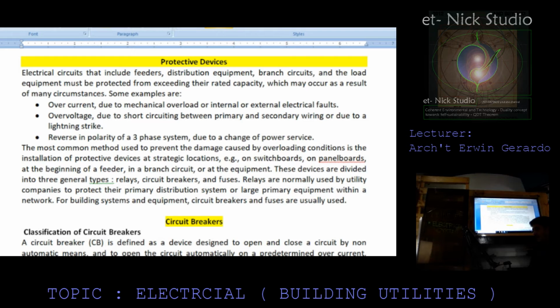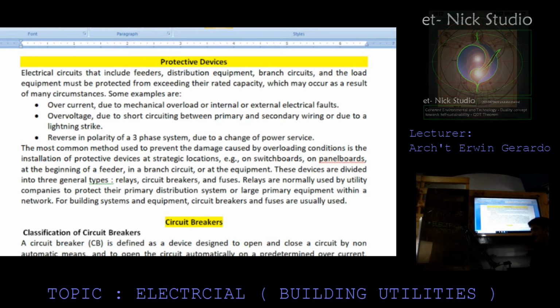The most common method used to prevent the damage caused by overloading conditions is the installation of protective devices at strategic locations. For example, on switchboards, on panel boards, at the beginning of a feeder, in a branch circuit, or at the equipment. These devices are divided into three general types: relays, circuit breakers, and fuses. Relays are normally used by the utility companies to protect their primary distribution system or large primary equipment within a network. For building systems and equipment, only circuit breakers and fuses are usually used.